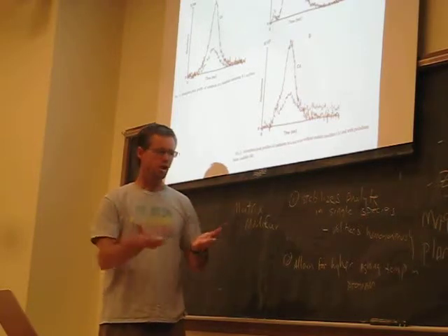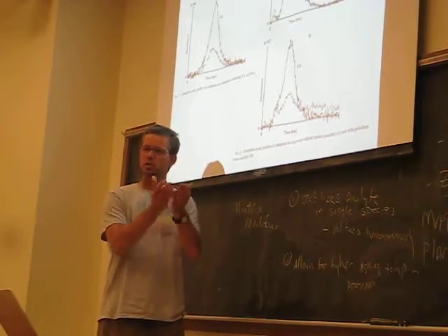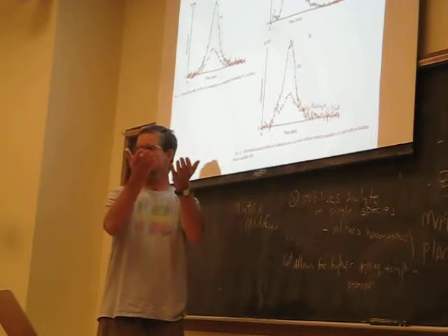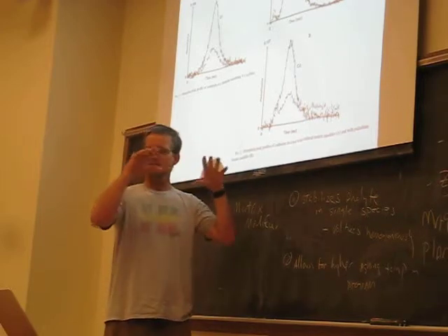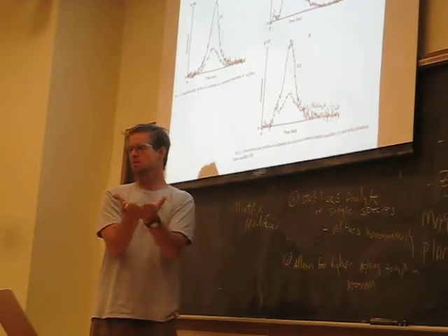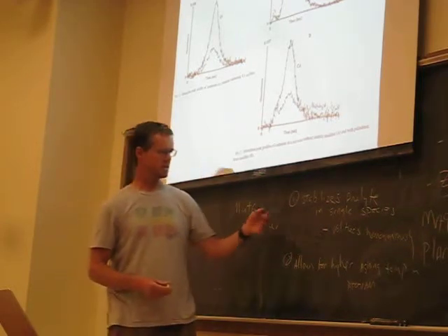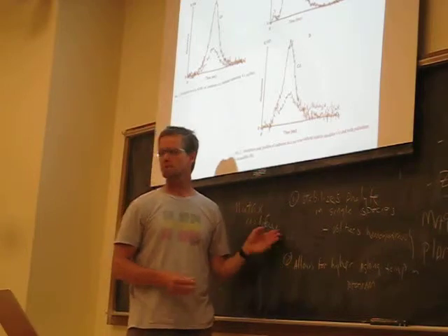And then they could char that sample at a much higher temperature and burn off and volatilize all the organic matter. So when they actually atomize the sample, the organic matter had been already burned off. And so the presence of interference was substantially reduced. Right? So the matrix modifier is allowing both those things, making them both possible. Okay.